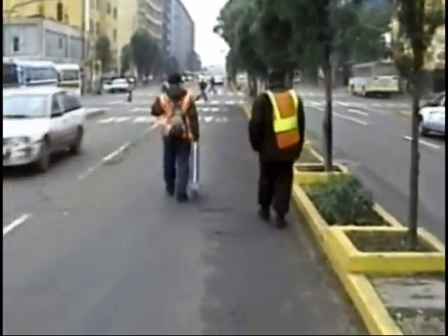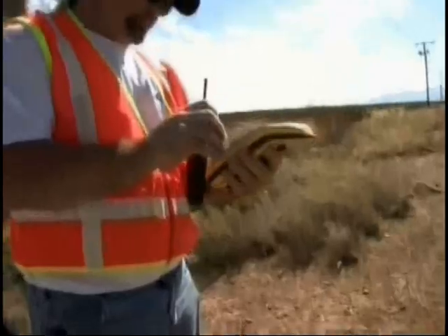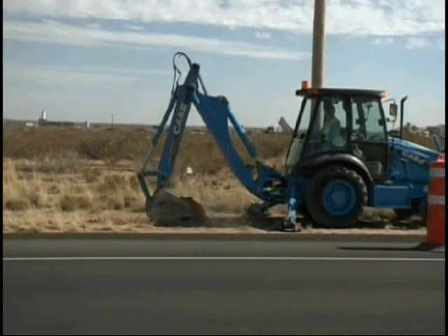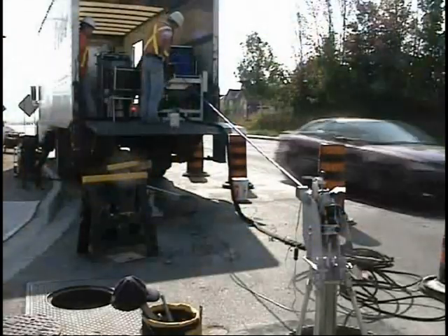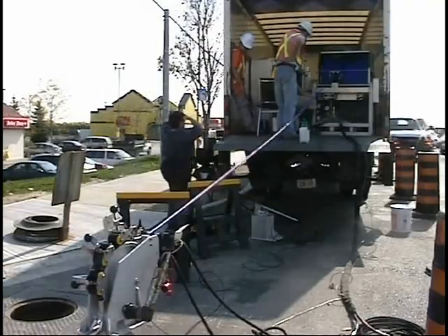The surface tracking device can locate the sensor to a depth of 30 feet, to ensure the precise location of all leaks on large diameter pipes. This precision is especially important in urban centers, where it allows smaller excavations to be made when repairing leaks.